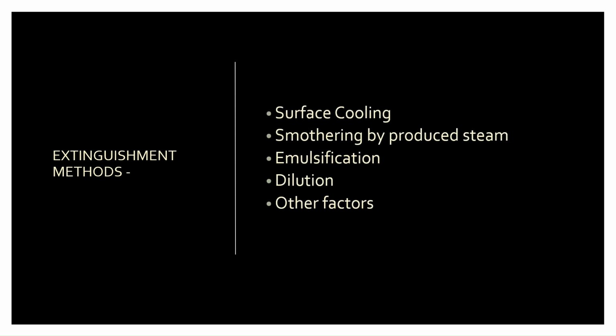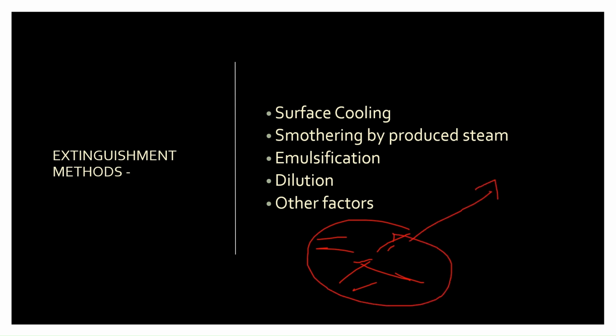So coming back to the extinguishment method, if you look at your screen, we have surface cooling. So it means water spray systems do more than just drench a fire, they cool the surfaces and smother flames by producing steam, break down flammable materials through emulsification, and dilute hazardous chemicals, all of which plays a vital role in slowing or stopping fires. It's not just about putting out the flame, but it's about controlling them from every angle. I hope you understand this particular concept. If you have any queries, you can just put in your comment section and let us discuss further.